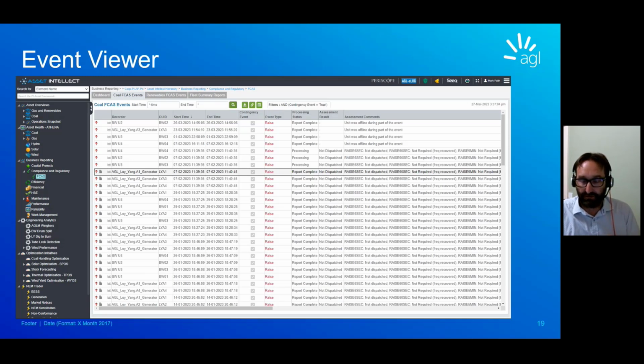So what we do is we have our data coming in from site, which is normally 1 second data. But then what we've been able to do is pull in our high frequency data from our protection relays. And that gets pulled in every couple of hours. And then we run a Python script over it. And we also use Pi to help create an event frame.